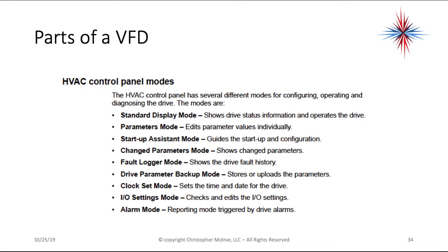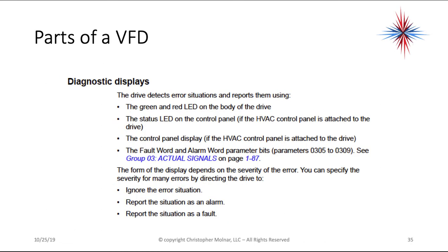Again, important because if you need to change out the VFD, you want to be able to just reload your existing control sets. You have a clock set mode. It sets the time and date for the drive. You have an I/O settings mode. It checks and edits the I/O settings. You have an alarm mode that reports. It's a reporting mode triggered by drive alarms. Diagnostic displays are also available.